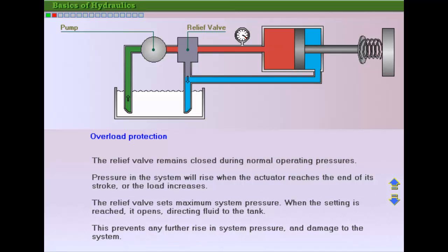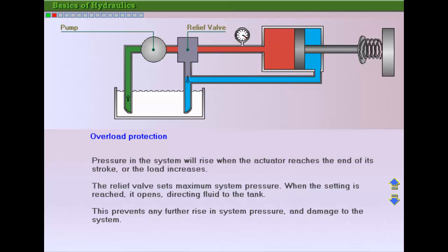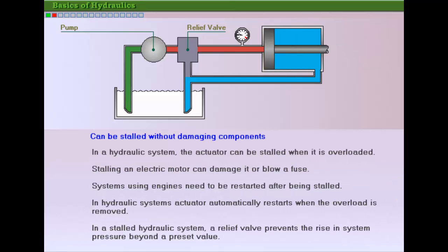This maximum setting of the relief valve determines maximum force capability of cylinders and torque capability of motors. In a hydraulic system, the actuator may be stalled when it is overloaded without damage.